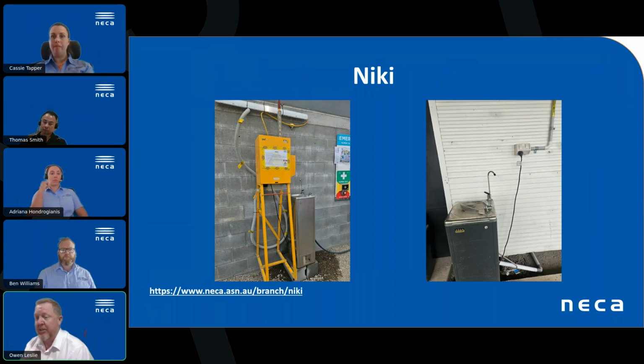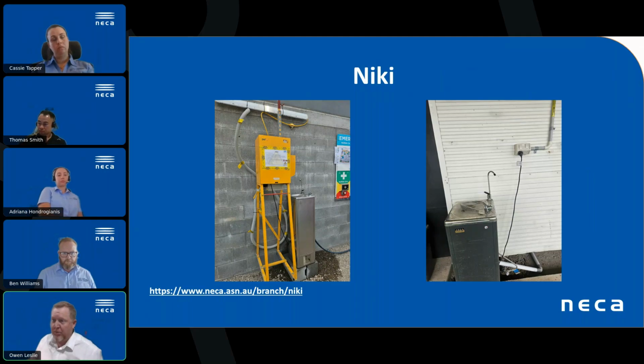I've got two images here, and this came up as a question on a construction site. It was the water fountain proximity to the construction switchboard, and then again the water fountain proximity to the weatherproof GPO. The question was, is this compliant or non-compliant? Both the construction switchboard and the weatherproof GPO are IP rated and weatherproof.